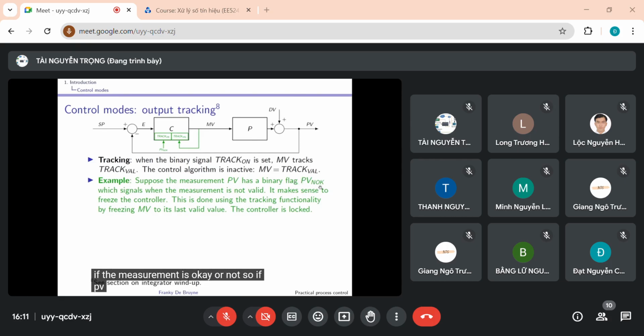So if PV NOK here is 1, this means that the measurement is not valid. Well, if this sensor is giving you this flag, PV NOK is equal to 1, this means that the process value measurement is no longer valid, and of course you cannot use it for control. So what you should do is freeze the controller. This can be done as follows. You connect the PV NOK signal flag coming from the sensor to track on, and you connect MV, the output of the controller, to track value.